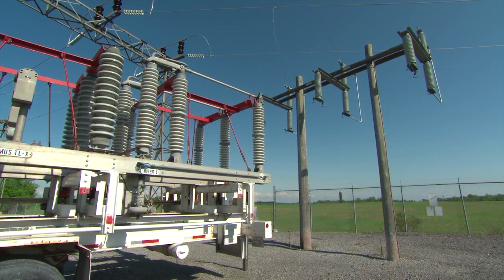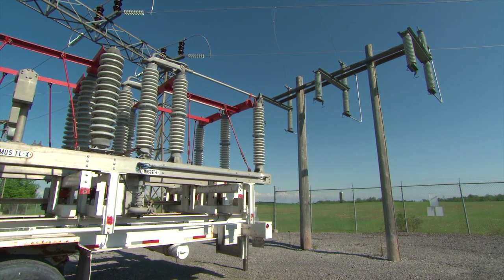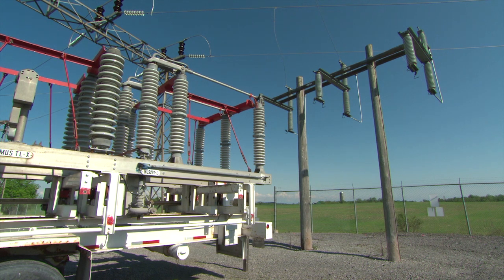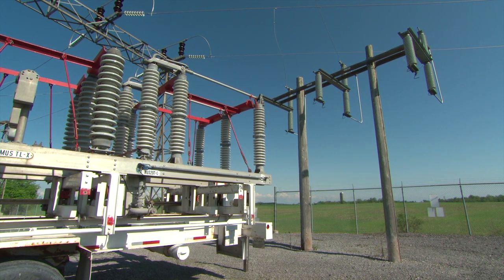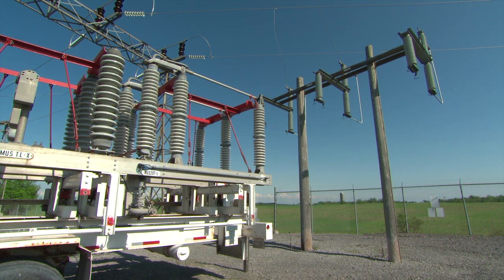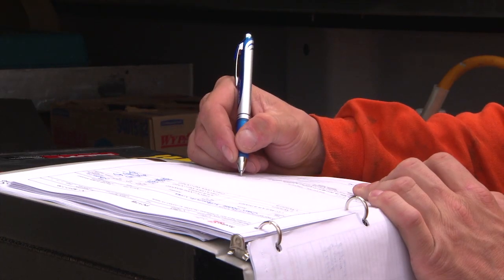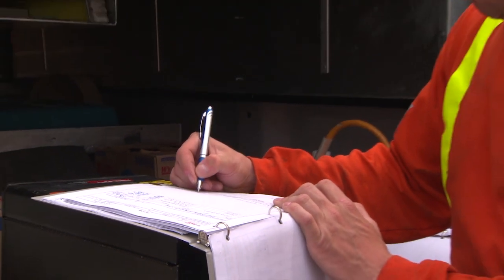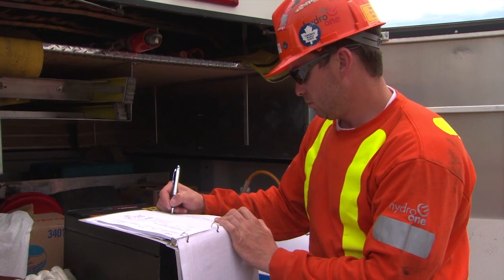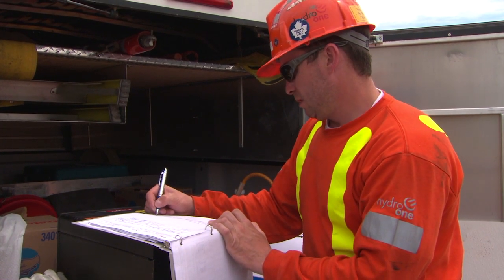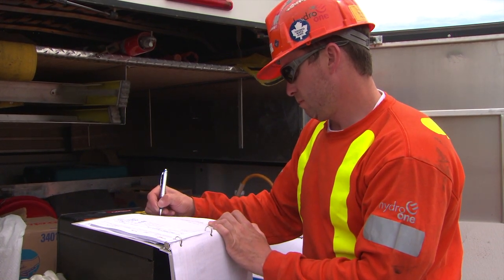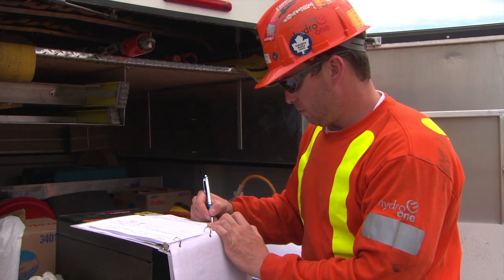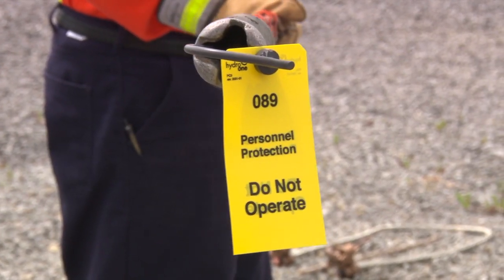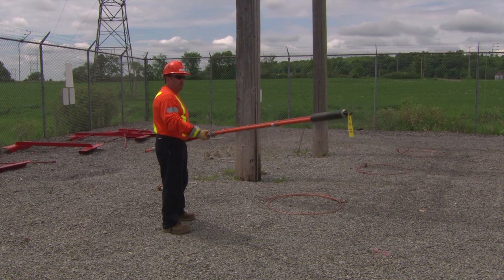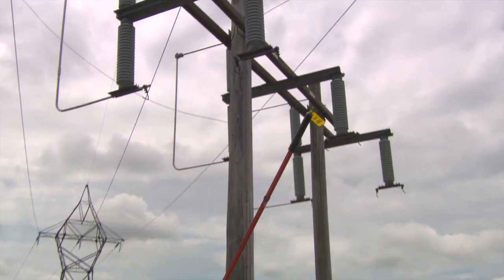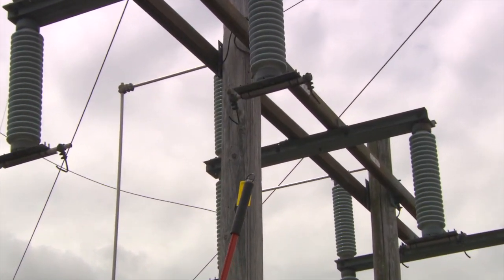Let's go back to the MUS-29 example and review the procedure for installing this 115 kV MUS at Battersea DS, a U70 station. Prepare a PC-17B work permit to isolate the MUS. This will provide a safe work area to fabricate and install the high-voltage leads. Check all 3 LC-MUS jumpers are removed, and then install 3 tags to confirm them removed.